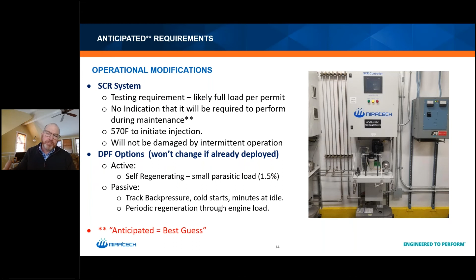If you have an active DPF, it's self-regenerating - you don't really have to change anything about your operations. If you have a passive DPF, there's a monitor on there that tracks back pressure. You should monitor your number of cold starts, minutes at idle, and then load that generator as needed to regenerate the filter.